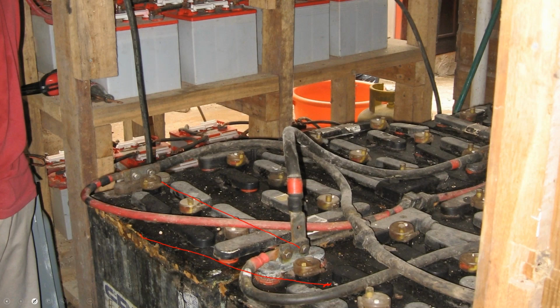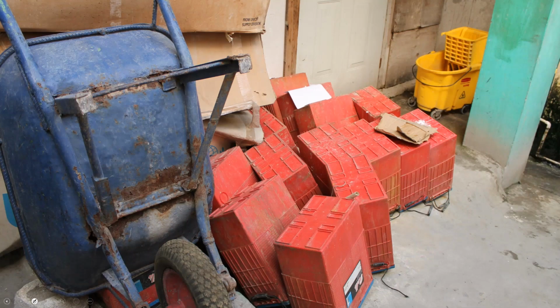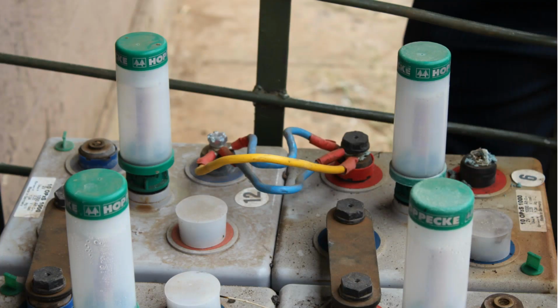All right, another question. When I checked the specification sheet, for example the 2KS33P, I did not see the three voltage charge levels: bulk, absorption, float. Where can I find this information? That information is in our user manual, okay? The user manual has all of it. It's not in the spec sheets because we don't want to change spec sheets every single time we change a charging spec, because the charging specs do change from time to time.